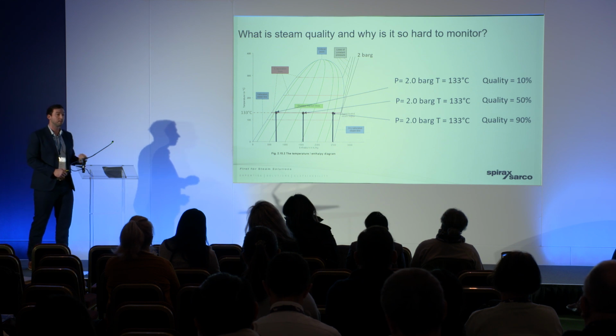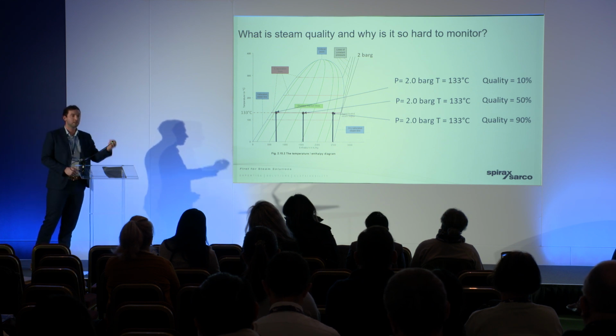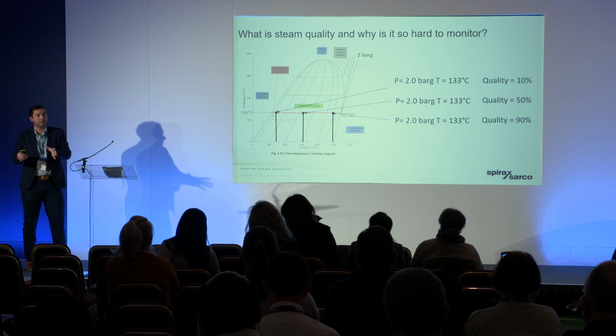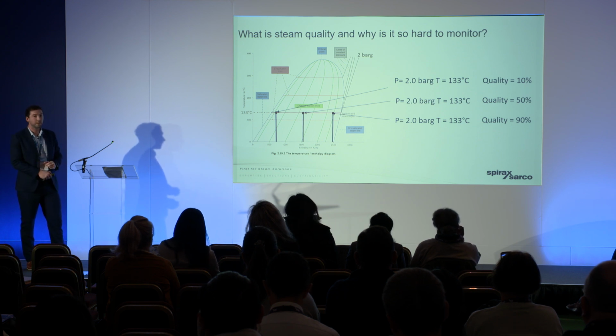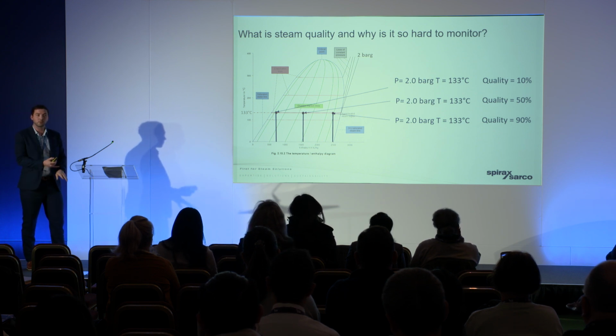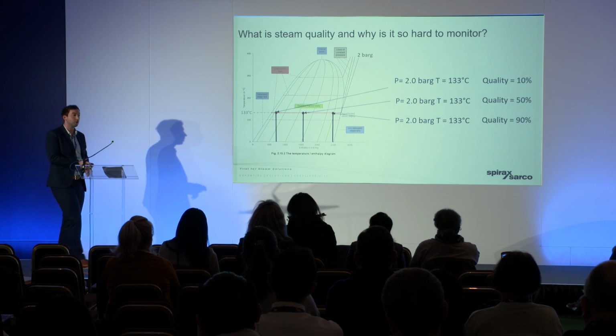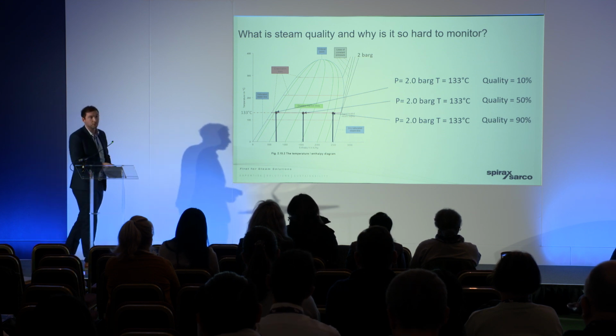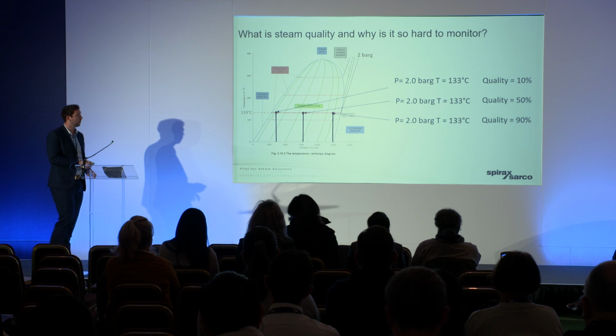That's why steam quality is so important. So when this meets surgical instruments, when it meets packs in your sterilizer, we need to make sure we've got maximum heat transfer, because that's what's killing our bacteria. That's what's making sure we don't have wet packs. That's what's making sure we don't have to reprocess our equipment.